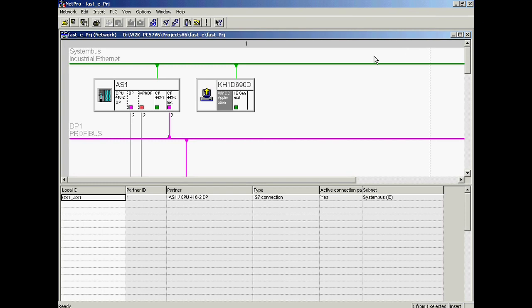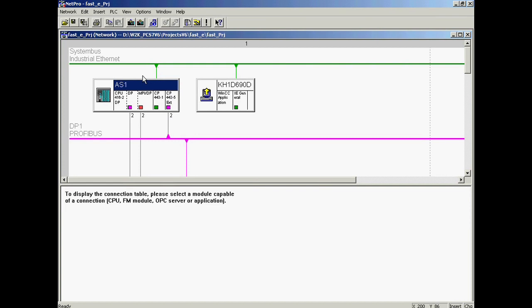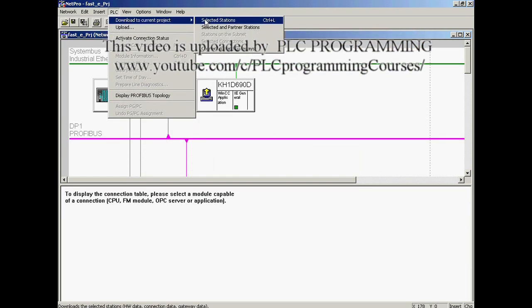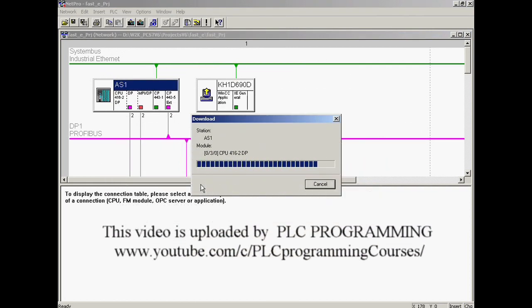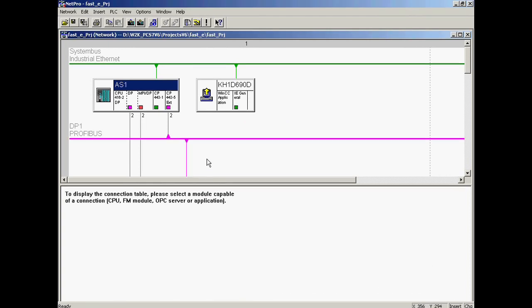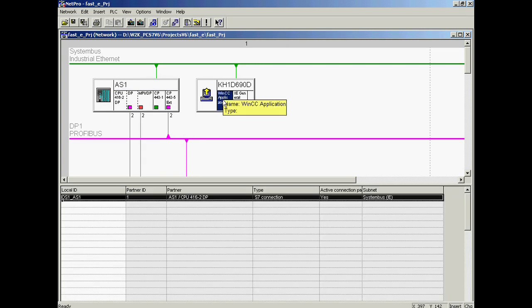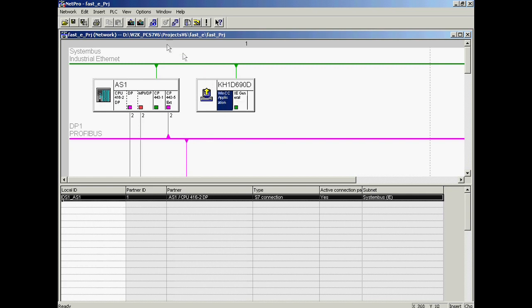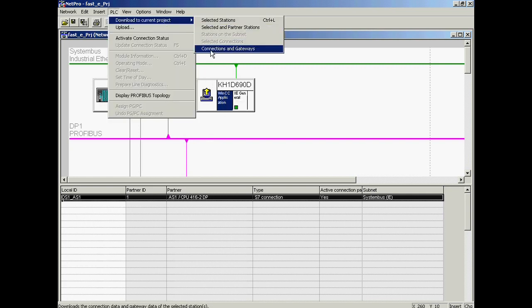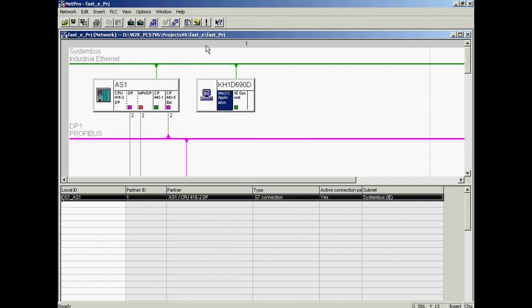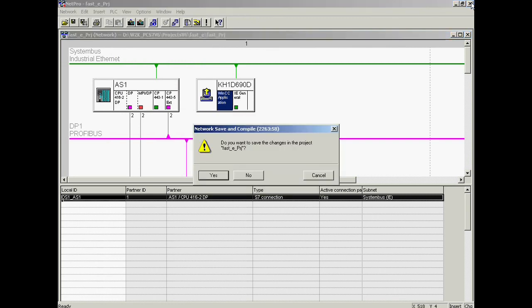Now the hardware configuration and the named connection are loaded into the AS. The AS is selected with the left mouse button and is then loaded. The CPU is again set to run status. In the last step, the named connection is loaded into the SIMATIC station — the WinCC application is selected and the connection is loaded. NetPro and HW Config are terminated.